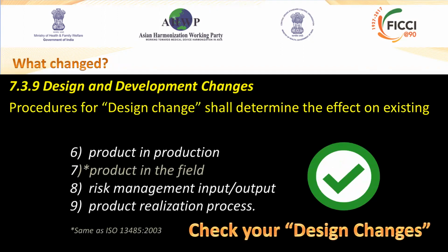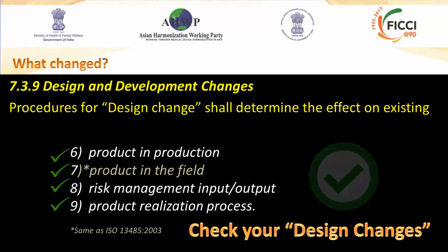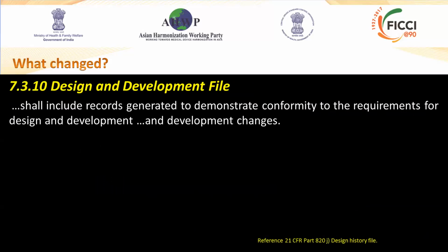And here's a few more, including product in production, risk management, input, output. It's really important to make sure that for any changes within the design control process, if there's any impact on the risk management process, those need to be taken into account during the design change. And that's similar to what's required in the EU.